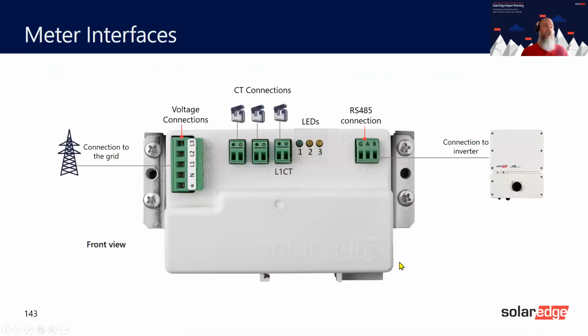Meter interfaces, so let's have a little look at it. As you can see, we've got L1, L2, and L3. If you do get them in the wrong order, it will give you the wrong information. Again, L1, L2, and L3, if you get the wrong order, you will get the wrong information. You can use this for single phase and for three phase as well. So don't worry about that.